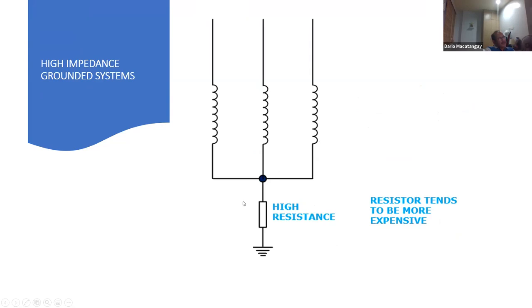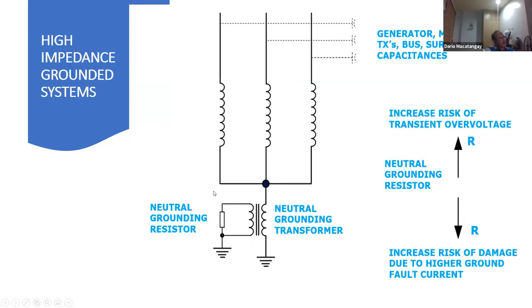Sometimes they use a high resistance directly connected to the neutral, but this neutral resistor tends to be more expensive than the setup here, which is using a neutral grounding transformer. Okay.